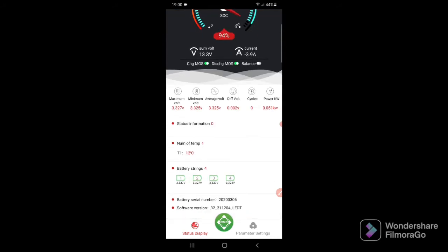So we have num of temp 1 - this is the temperature sensor connected to the BMS, and it tells me the temperature where the batteries are at the moment is 12 degrees. This is quite important for when charging, which once again you'll understand once we get into the full settings.